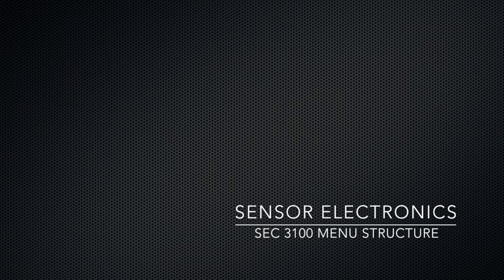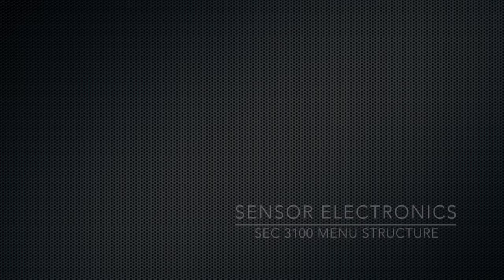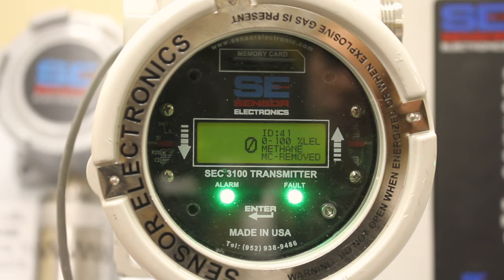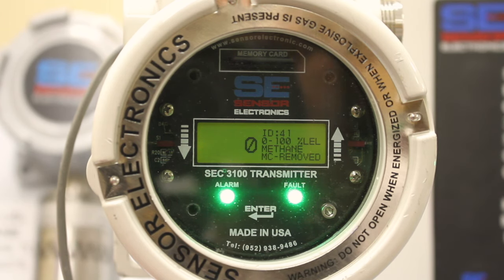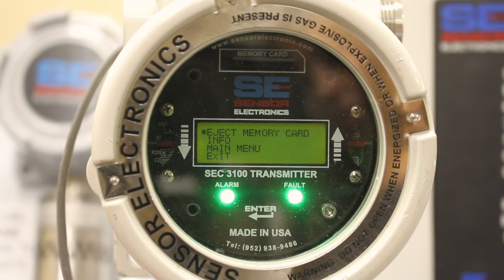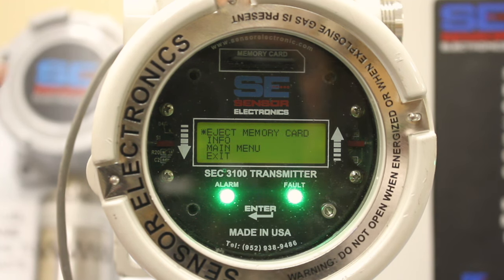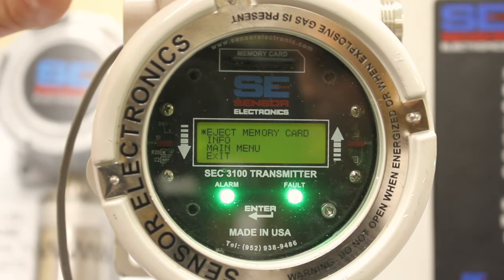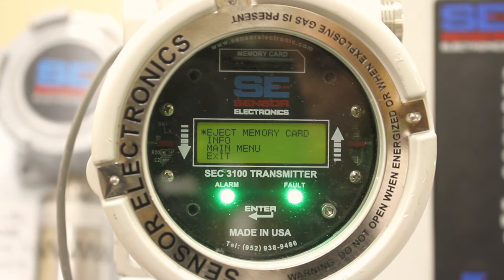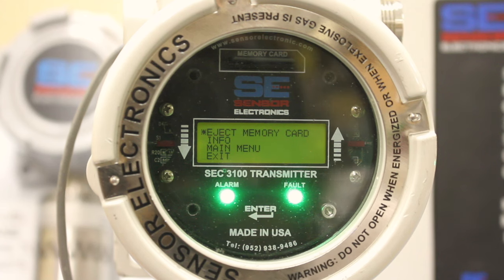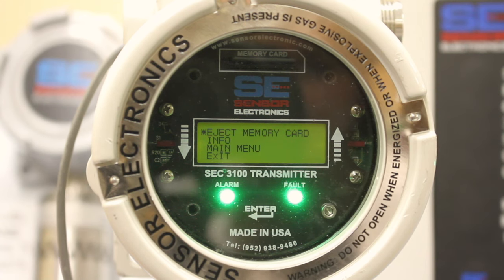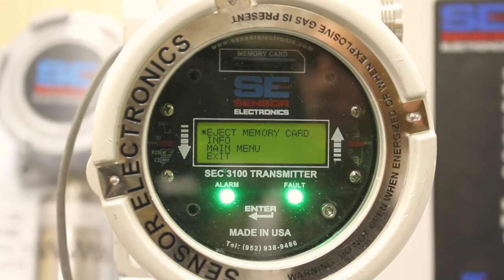This video will run through the SEC 3100 transmitter menus, and so it's a normal operation now. To get to the menu structure, you go to Enter, and the first one is Eject Memory Card. If you have a data card or memory card inside the transmitter, which this one does, you can select that one to actually pull the memory card out.